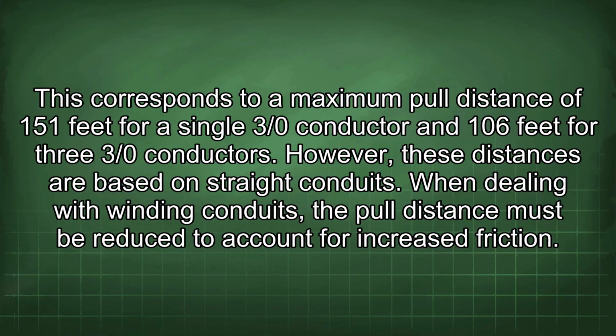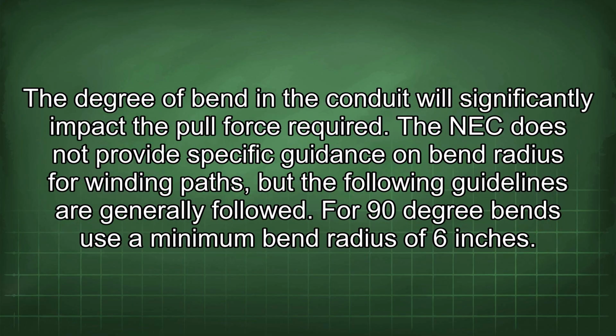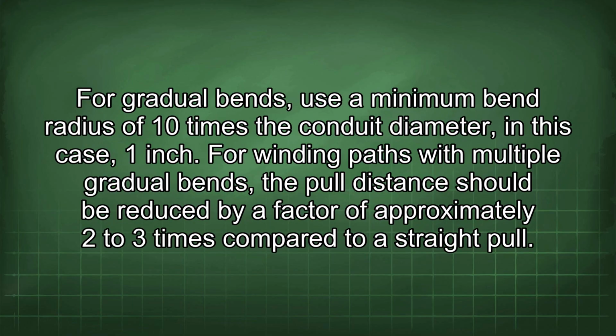When dealing with winding conduits, the pull distance must be reduced to account for increased friction. The degree of bend in the conduit will significantly impact the pull force required. The NEC does not provide specific guidance on bend radius for winding paths, but the following guidelines are generally followed. For 90-degree bends, use a minimum bend radius of 6 inches. For gradual bends, use a minimum bend radius of 10 times the conduit diameter, in this case, 1 inch.